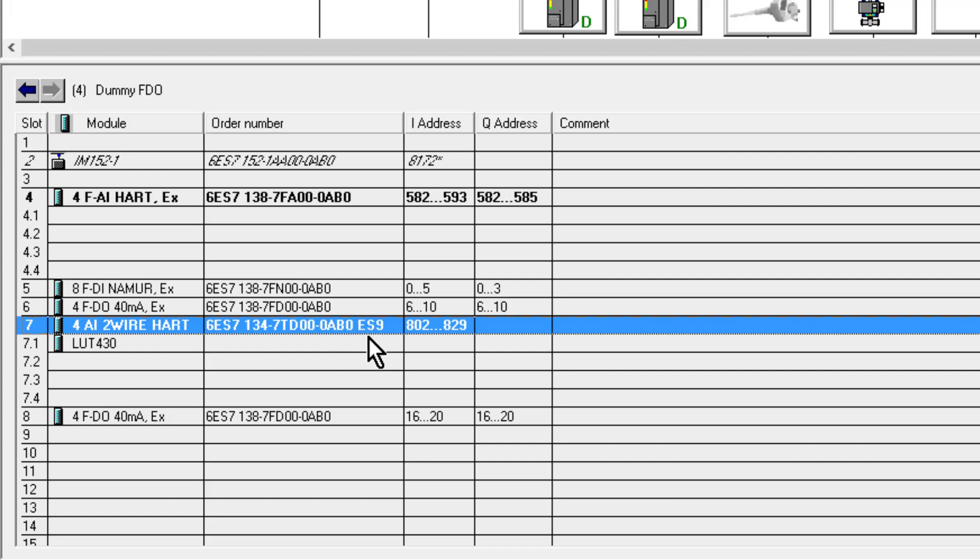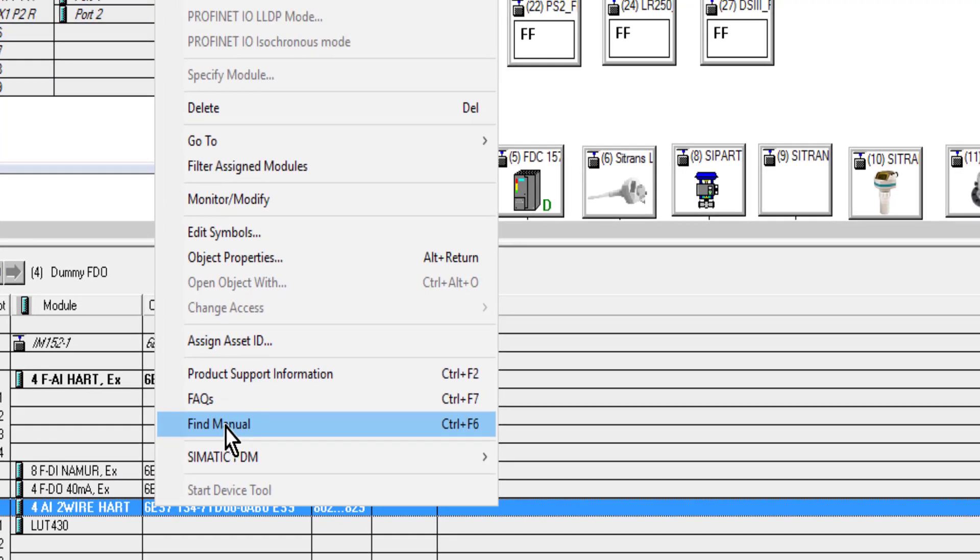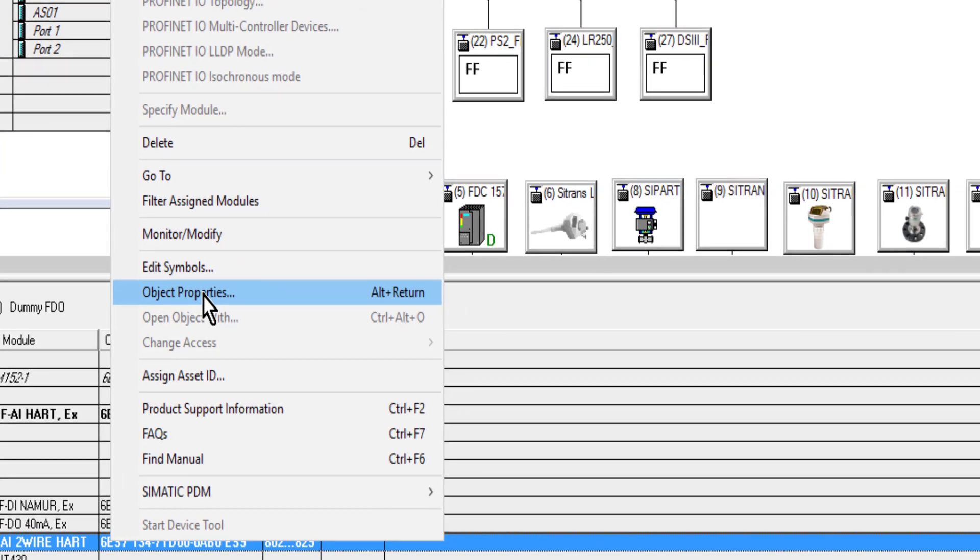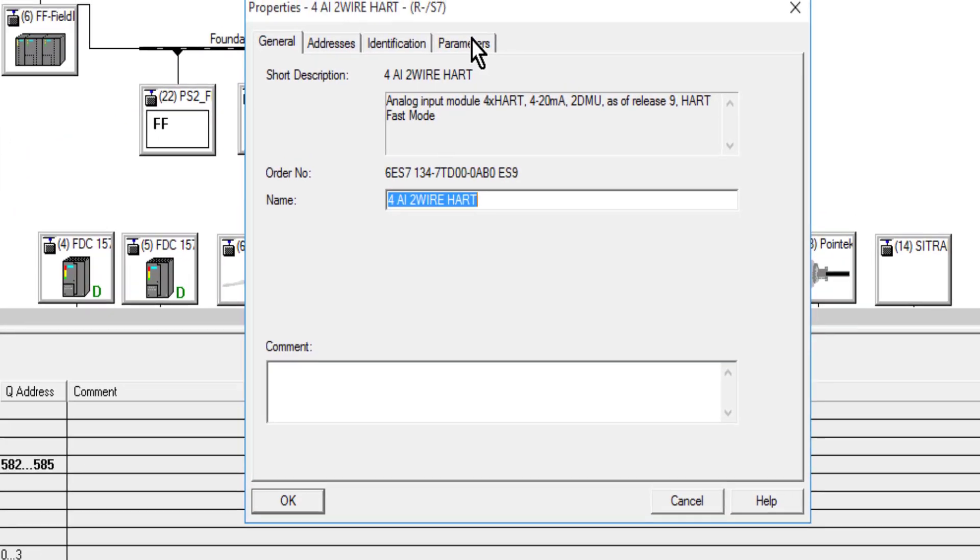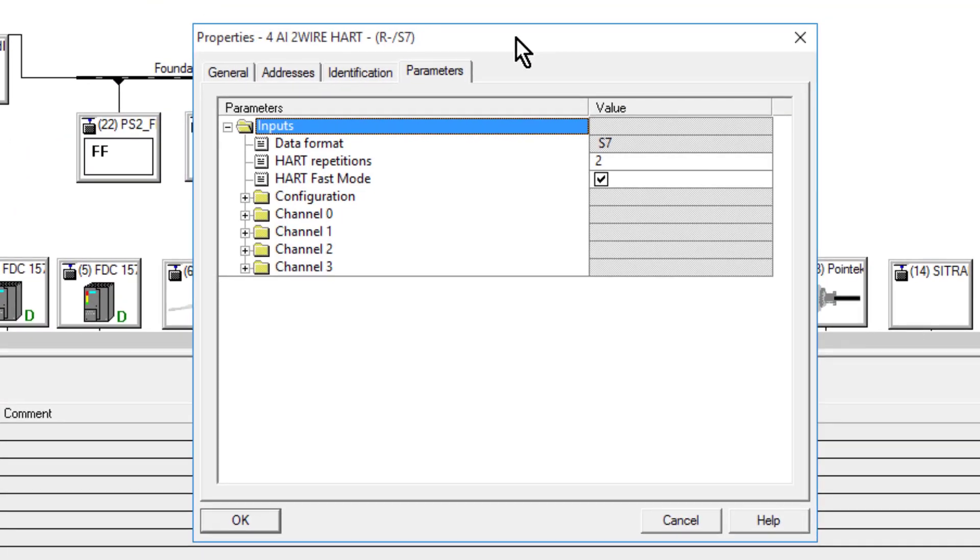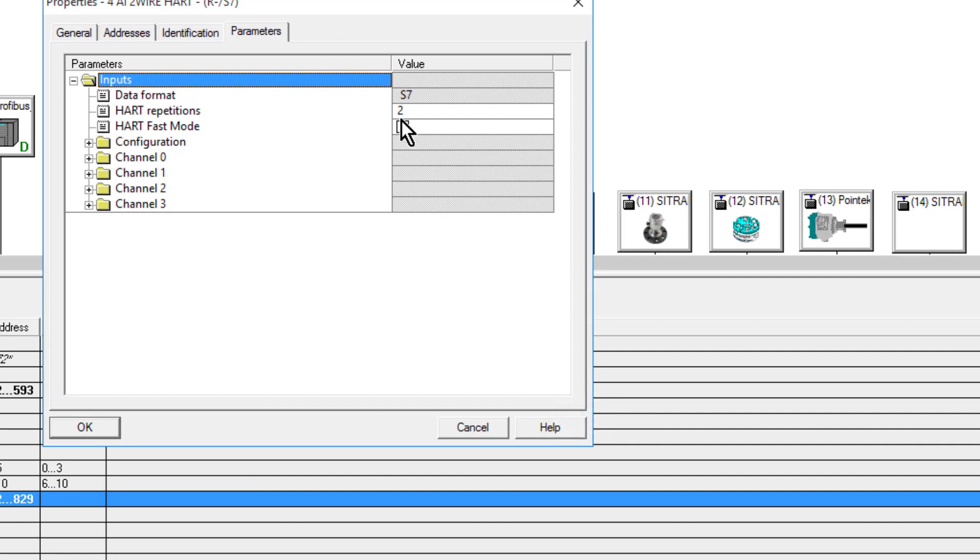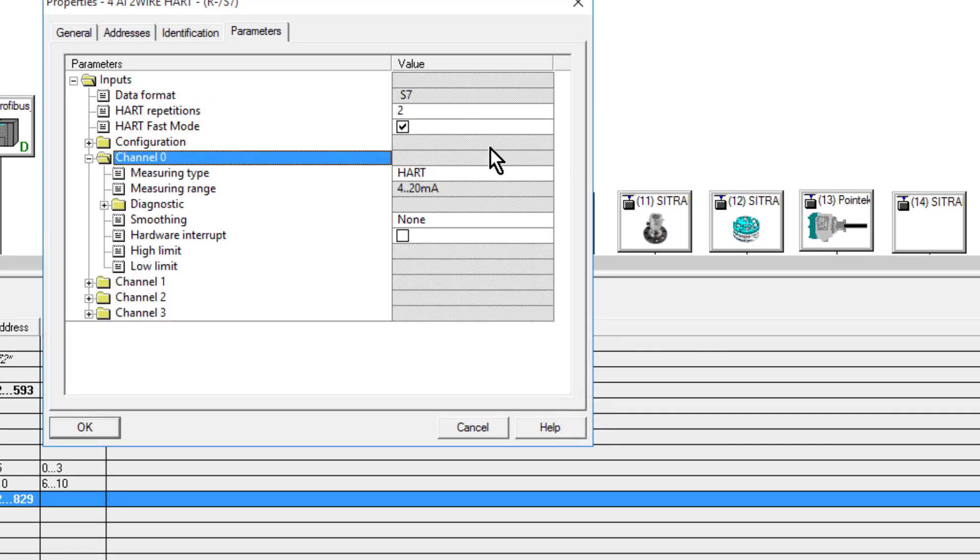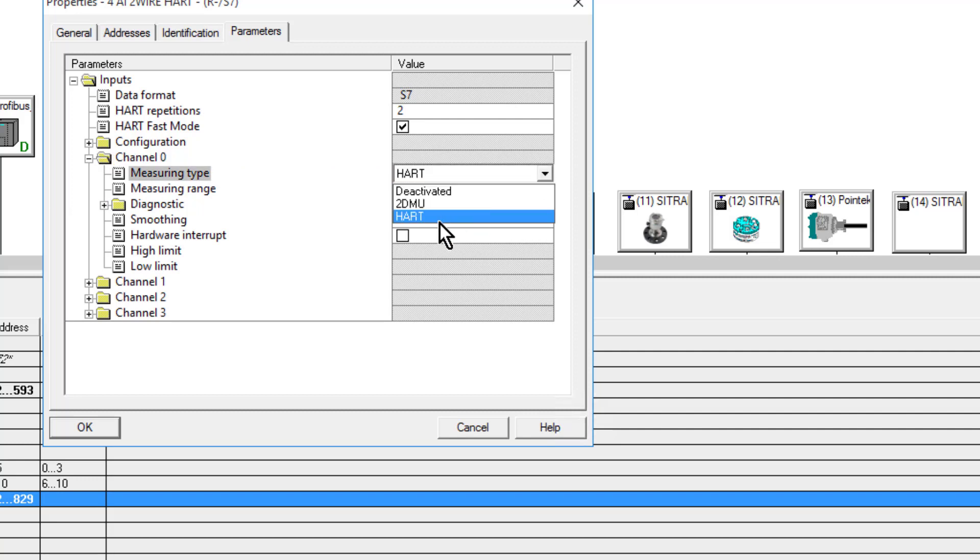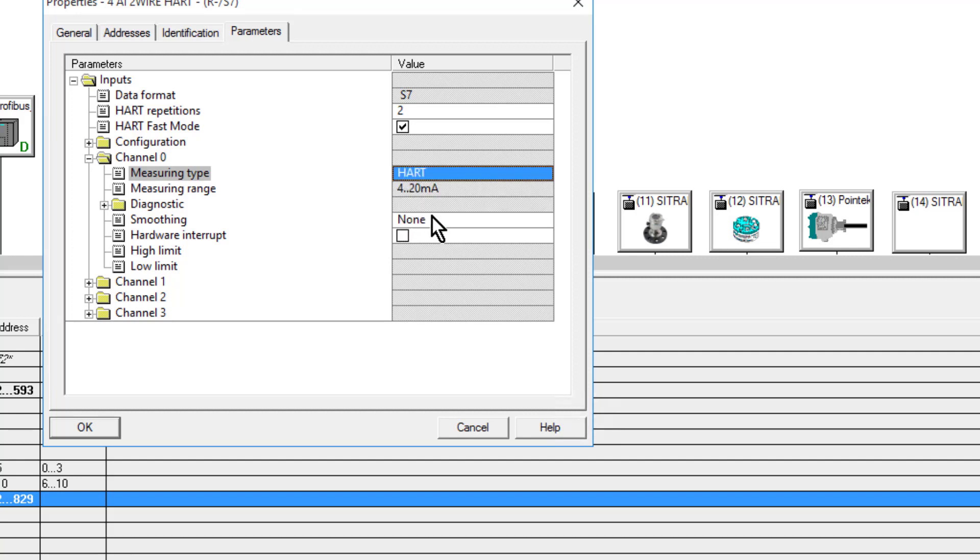You also need to make sure that we've got the ES9 option at the end here to support fast HART. If we go to object properties and then parameters, some things we have to do to enable fast HART—for each channel, if you have a HART device connected, we need to enable it for HART. By default it'll be on deactivated or two-wire, but we need to select HART. You'll still get the analog signal, but enabling HART will allow PDM to pass through this card down to the instrument.